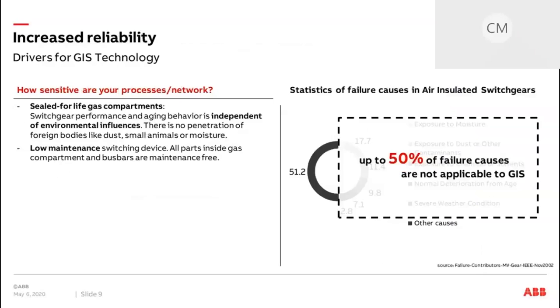For the same reasons just explained, that also means that the switchgear works much more reliable because you have sealed gas compartments and the performance is independent of environmental influence. Also, the aging is independent because they are all protected inside the gas compartment. So the probability for a failure is reduced, referring to a study from the IEEE committee from 2002. Roughly 50% of the causes for failure that apply to AIS do not apply to GIS.